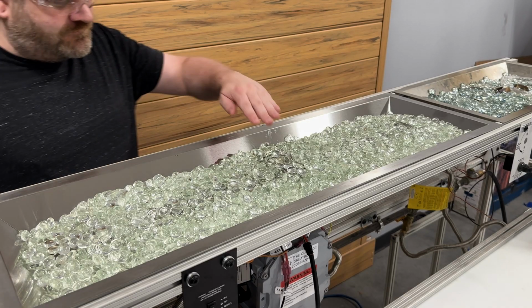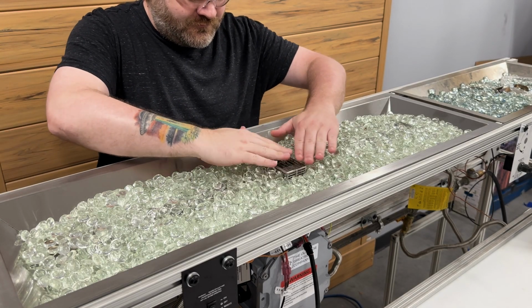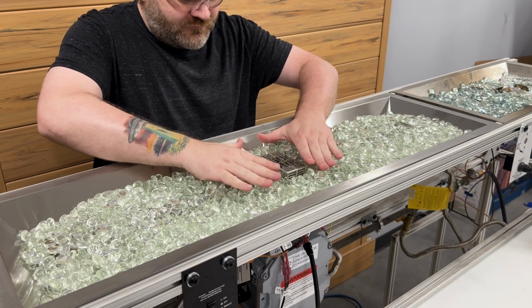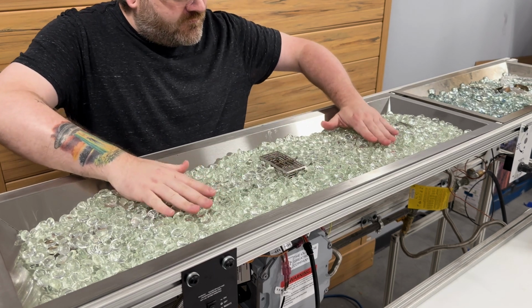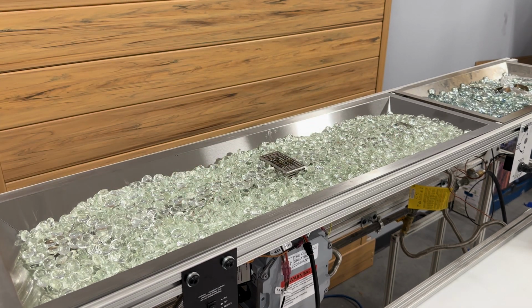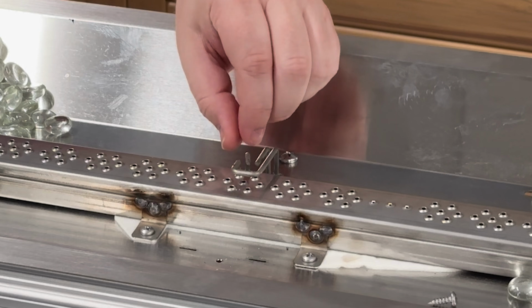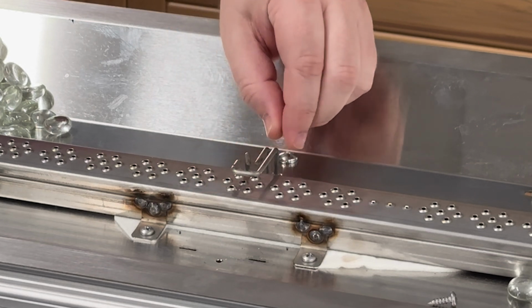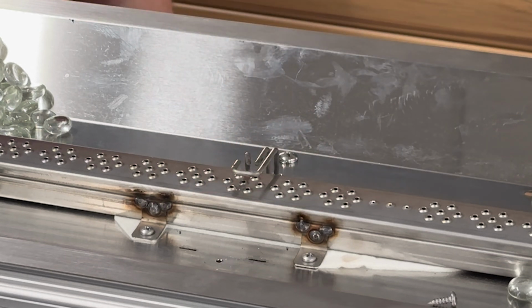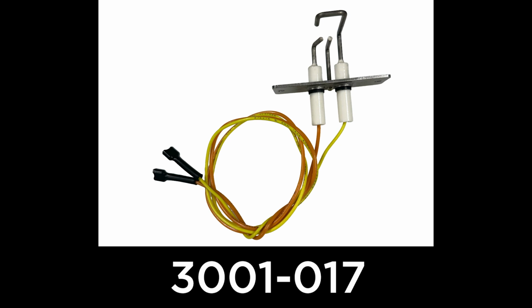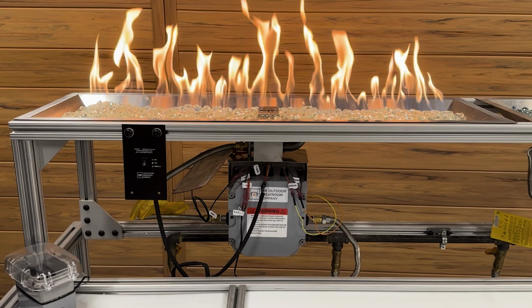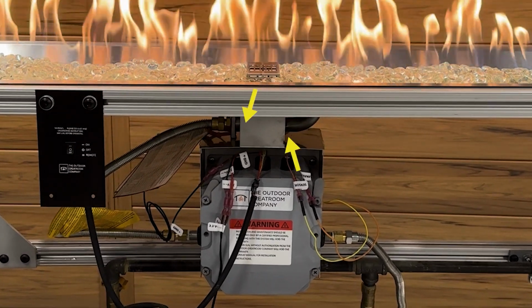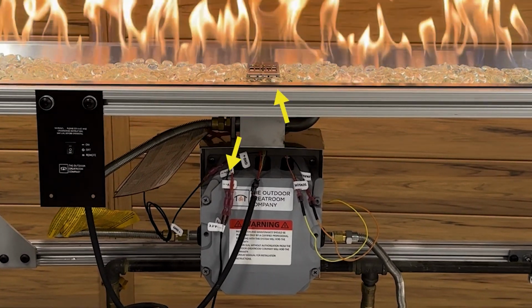First, ensure that the media instructions are followed properly and clear any glass gems, other fire media, and debris from the top of the ignition wind guard. If you don't do this, the flame may not hit the sensor and ground properly, resulting in nuisance shutdowns. Secondly, inspect the flame sensor rod and ground rod. If these are not secure, they may need to be replaced. Order part number 3001-017.